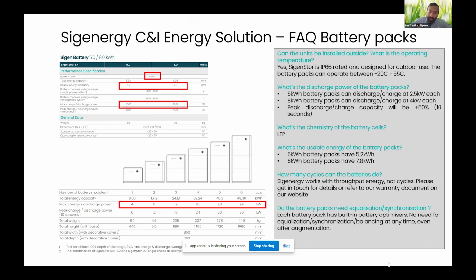Now, it is very important to understand that if you see the example on screen, let's say you have two 8 kilowatt hour batteries, which will account to 16 kilowatt hours of storage and 8 kilowatts of charge and discharge capacity. If you have only a 5 kilowatt energy controller there, then you will be limited by the energy controller when you discharge towards the grid, when you discharge towards the load, when you charge from the grid. Essentially, when you need the inverter circuit in the energy controller, when you do DC to AC conversion or when you do AC to DC conversion.